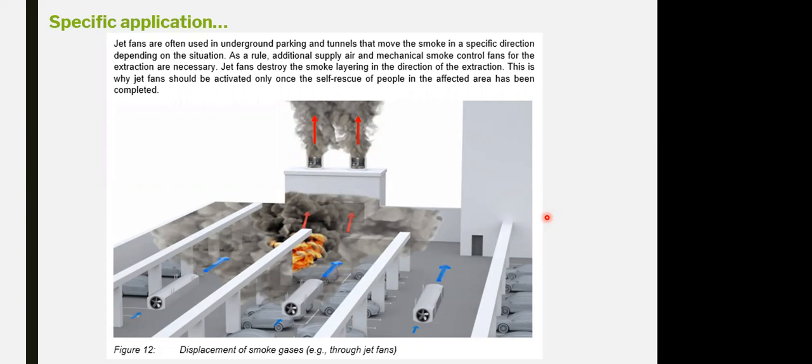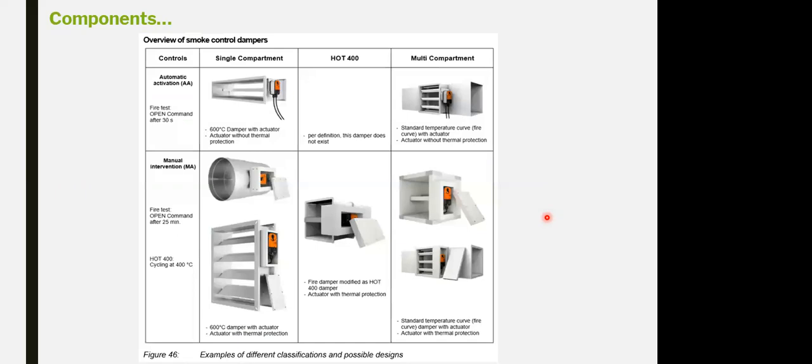Should be fire rated encasement for 2 hours for the minimum degree of 250 degrees. Another component for the smoke management system is the motorized smoke fire dampers. And the damper has to be as well for the 2-hour fire rated 250 degrees operation, including the actuator for the dampers itself. Dampers should be motorized dampers or should be connected with a fusible link, with the temperature.